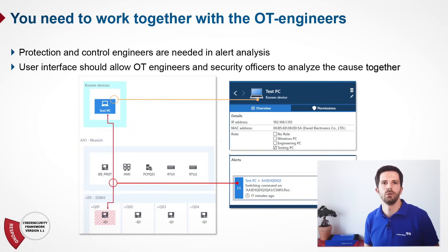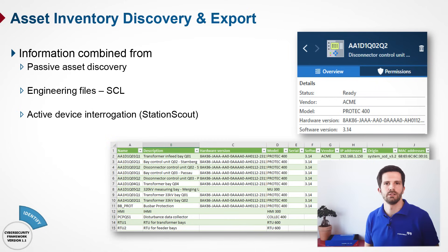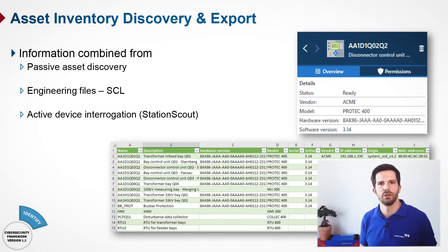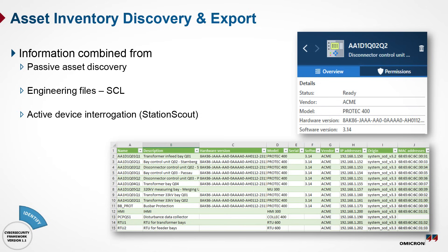Another important topic in OT security processes is asset inventory. It is important for risk identification to know what assets are communicating and what firmware versions they are running in order to perform a risk analysis. Station Guard can export this asset inventory automatically, detecting all assets in the network based on passive traffic analysis. Combined with engineering files, it provides a detailed description of all assets, their firmware versions, and other parameters such as proper device name and description.